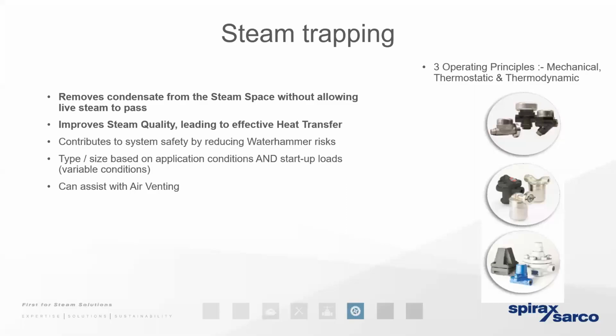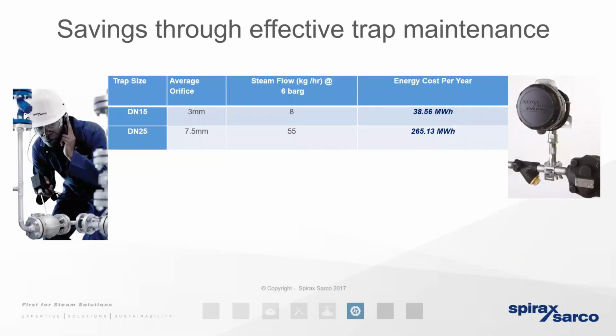Perspective, the biggest threat of a steam trap being failed is when it's failed in the open position. And when a steam trap's failed in the open position, we've got that steam that basically passes across the orifice, and it is going to find its way to a vent. Now, typically those vents are going to be sited on the top of condensate receivers. So if we've got that live steam being vented away to atmosphere, obviously it's a huge loss of energy.